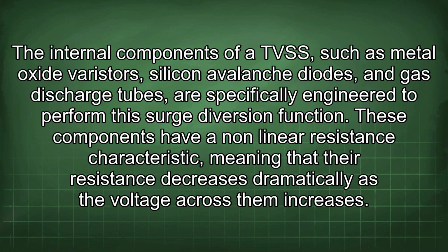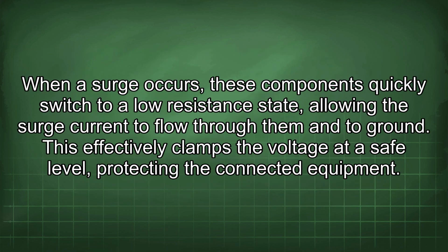The internal components of a TVSS, such as metal oxide varistors, silicon avalanche diodes, and gas discharge tubes, are specifically engineered to perform this surge diversion function. These components have a nonlinear resistance characteristic, meaning that their resistance decreases dramatically as the voltage across them increases. When a surge occurs, these components quickly switch to a low resistance state, allowing the surge current to flow through them and to ground. This effectively clamps the voltage at a safe level, protecting the connected equipment.